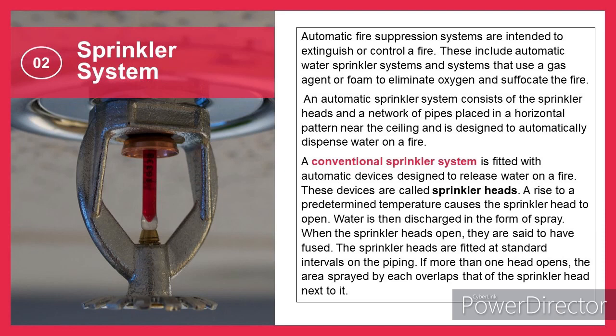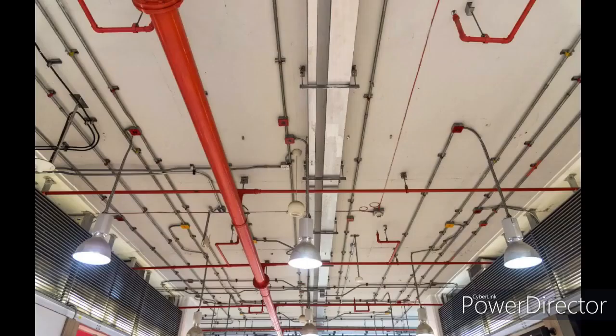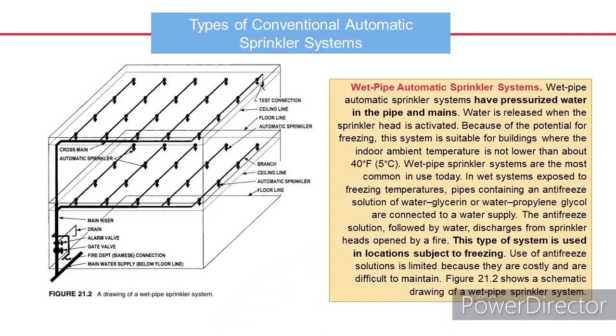A rise to a predetermined temperature causes the sprinkler head to open. Water is then discharged in the form of spray. When the sprinkler heads open, they are said to have fused. The sprinkler heads are fitted at standard intervals on the piping. If more than one head opens, the area sprayed by each overlaps that of the sprinkler head next to it. Here are the types of conventional automatic sprinkler systems. First type is the wet pipe automatic sprinkler systems.